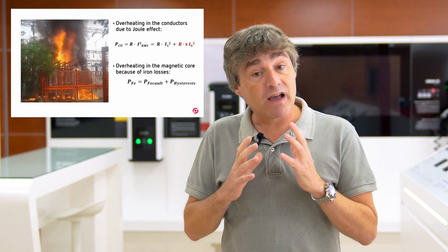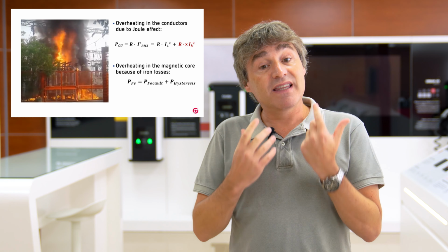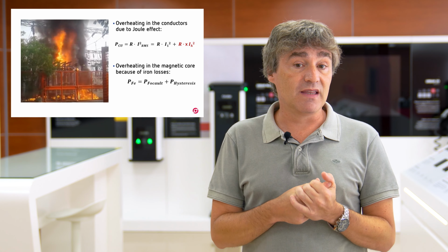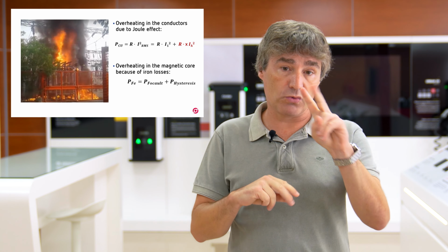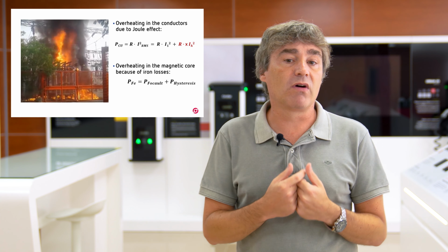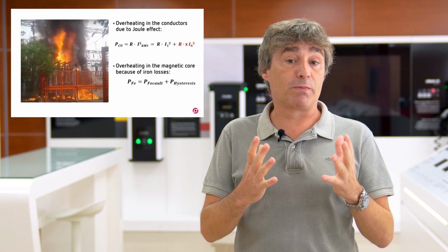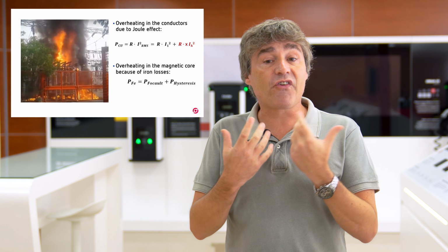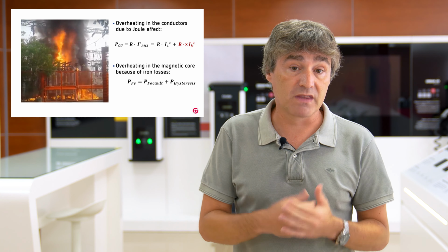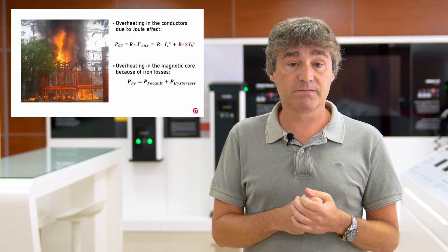So the presence of harmonic currents running through the transformer windings will make these losses rise. This may lead to basically two effects. One is a poorer voltage quality, reflected in high voltage distortion rates, affecting the correct operation of supplied loads. And the other is the rise of the transformer temperature that may cause the derating of the power transformer capacity.